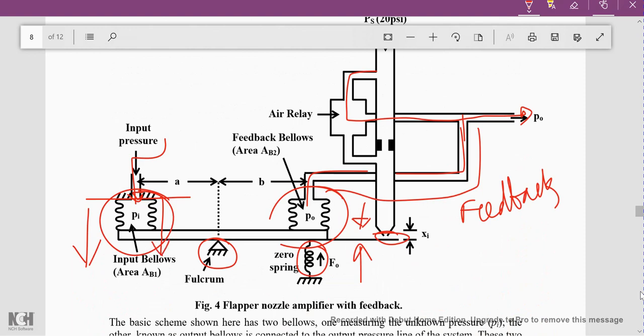Because it is fixed at this position, the bellow expands and pushes that side of the beam downward. Due to this, a counter force acts on the right-hand side, moving the flapper towards the upper side. When the flapper moves upward, this opening near the nozzle will be closed, causing the pressure here to increase.